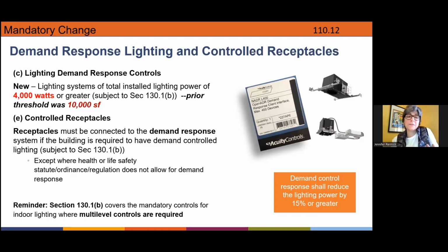And to put that in perspective, using an office building as an example, that 10,000 square foot office building might trigger, or a 10,000 square foot warehouse or retail would trigger for sure. But now, like 4,000 watts, you could easily get that in a 7,000 square foot office building. And you could easily get that in even smaller, like a retail or warehouse. It might be around 6,000 square feet. And there are some new controls too with the receptacles, meaning that if your building has to have the demand response for the lighting, now that's going to affect certain receptacles. And the lighting demand response still would have to reduce everything by 15% or greater.